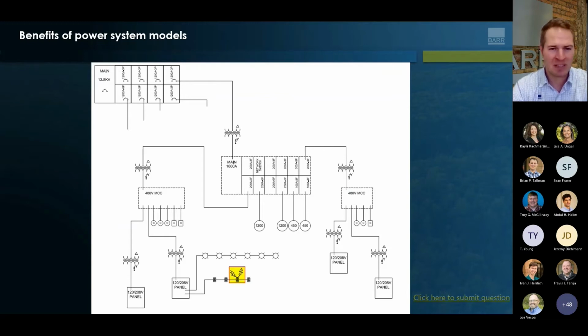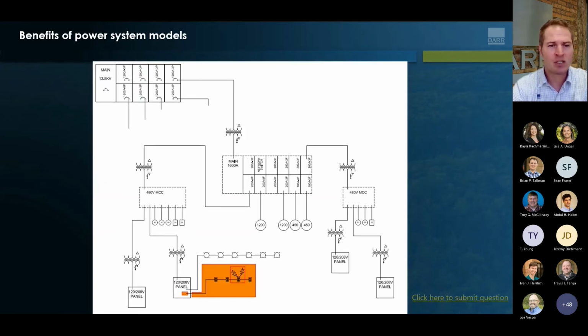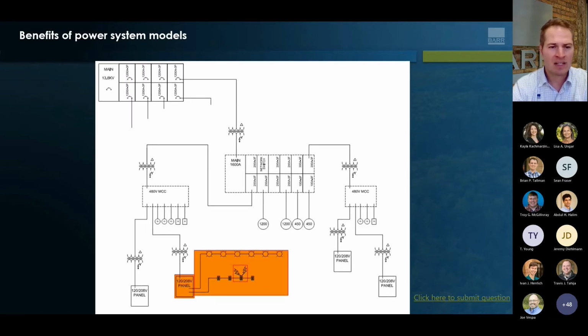So this is a mock-up, not the same single line, but just for the sake of talking through this, this is the level where a trip occurred on a small transformer tail end of the power system. If it had been coordinated properly, then a breaker at this 120 or 208 volt panel would have tripped, and just this circuit would have gone without power. Wrong settings in that breaker could have tripped the main breaker on this panel, and all of this would have been without power.